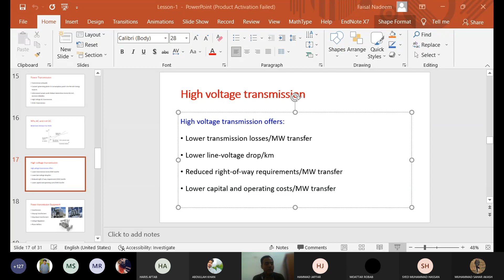P is equal to I square R, this is the power loss equation. So if voltage increases and I decreases, then the square of I will be less. However, if I increases, for example take I equal to 4, the square of 4 is 16. We have to take the square of the current as in the formula. So if the current in the line increases, say before it was 4 and now it is 5, the square of 5 is 25. So the current increases by just 1 ampere, but in the formula, the losses increase from 16 to 25.